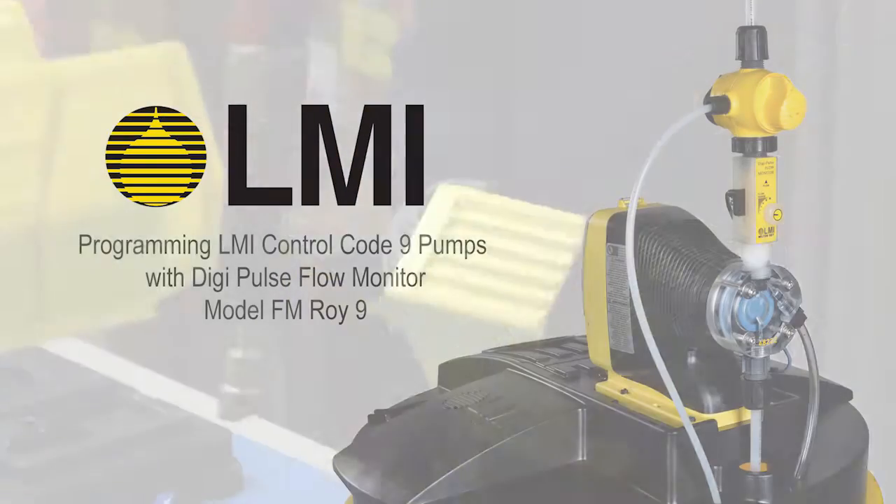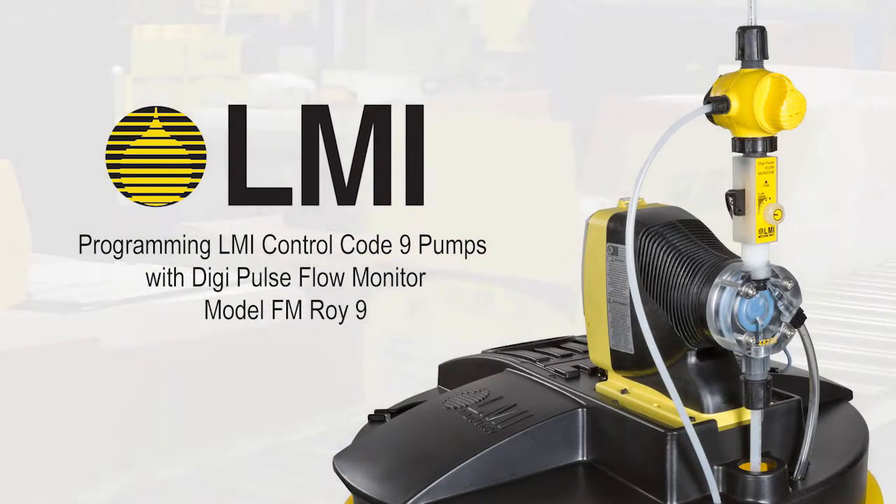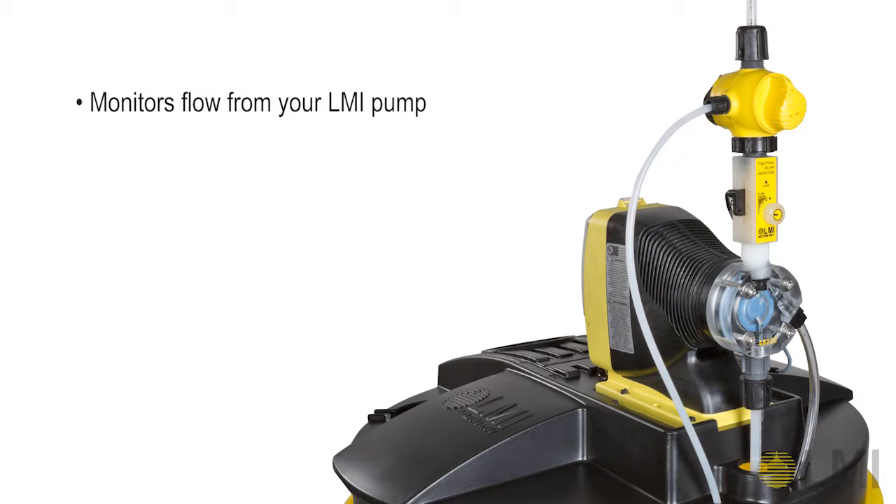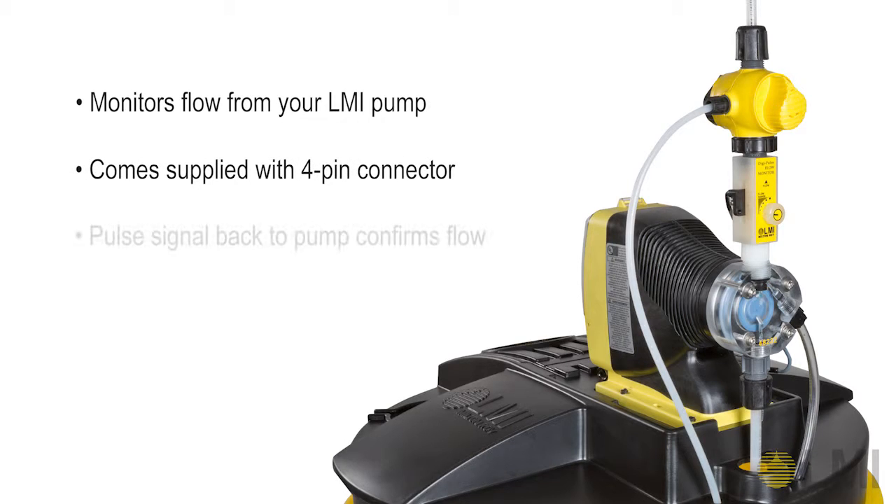Programming LMI Control Code 9 pumps with DigiPulse Flow Monitor, model FM-Roy9. The FM-Roy9 DigiPulse Flow Monitor is designed to monitor flow from your LMI pump. It comes with a 4-pin connector for interfacing with your Control Code 9 pump. The flow monitor delivers a pulse signal to the pump for each successful pump stroke registered.